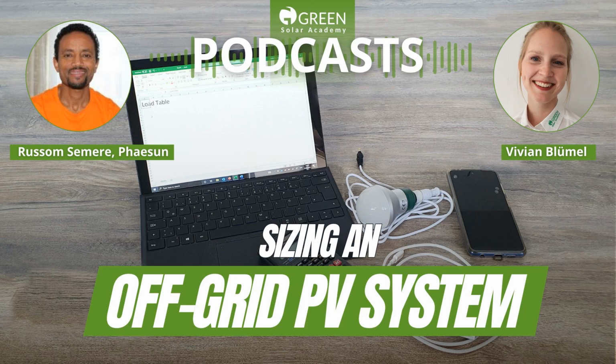Another important thing is all of them should have the same battery voltage. So depending on the size of the system, you can design a 12 volt system, a 24 volt system, or a 48 volt system. And so if you have a 24 volt system, the battery should be 24 volt minimum, and the charge controller should be a 24 volt charge controller, and the same for the module and the inverter. So all of them must have the same system voltage.